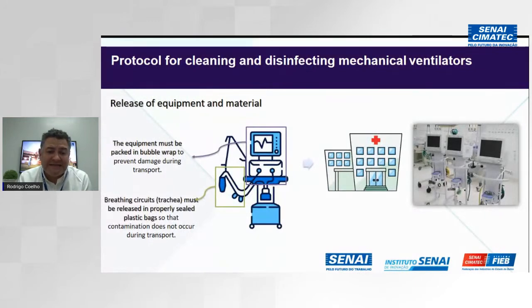So in order to release the equipment after the maintenance, what we are doing here is packing the whole system in bubble wrap, where the equipment will be protected against any shock during the movement. And the breathing circuits are properly sealed in a plastic bag and go along with the equipment. Please remember, never split the pieces of the equipment. It must travel through the whole facility in a single box, where all the components and all the pieces of a single machine are always kept together.